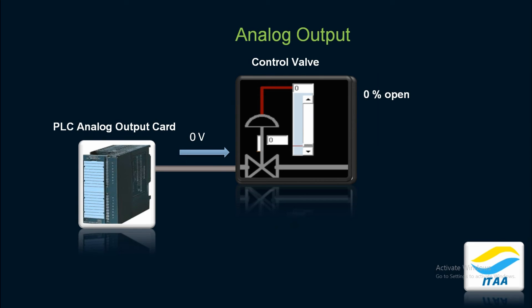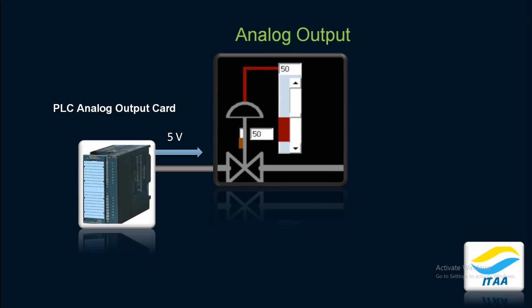Now, from the analog output card, the signal will travel to the final control element — in this case, a control valve. If the PLC sends 0V to the control valve, that means the PLC has ordered the control valve to open 0%. Again, same principle: 0V means 0%. If the PLC sends 5V from the output card to the control valve, that will be a 50% opening order — telling the control valve to allow 50% of the flow.